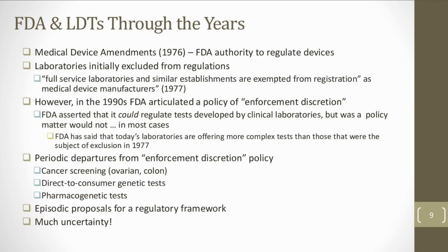So we've been in a period of mostly enforcement discretion for a number of decades, with periodic and sometimes sudden departures from that policy for tests that FDA views as posing higher risk. For example, labs offering tests for cancer screening, direct-to-consumer genetic tests, pharmacogenomic tests. These are examples when FDA has expressed concern, and the way FDA generally expresses concern in the first instance is by sending a warning letter to a laboratory that is offering the test, saying this is a medical device, and if you want to offer it, you need to get appropriate premarket review. There have been episodic proposals by FDA for a comprehensive regulatory framework that have not to date come to fruition. But as comes as no surprise to anybody on this call, I'm sure, this has generated much uncertainty over many years in the laboratory community.